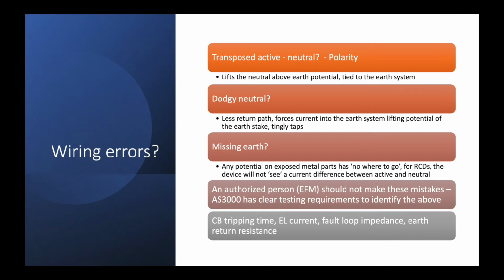The other thing is, I talked about the transpose active and neutral. That's a polarity check. So when you get your distribution utility or your contractor to come and hook up the power to your house, they have to do a polarity test to make sure the active and neutral aren't swapped. So you really need that neutral to be in the right spot for your earth leakage to work. It's also relying on, in an overhead area, every fifth pole you'll see a down lead coming down. That's connected to the neutral wire on the overhead. So it's relying on that wire, that conductor in the ground, for the return current to go back. Right? So without that and an earth stake in your house, there's some serious issues.